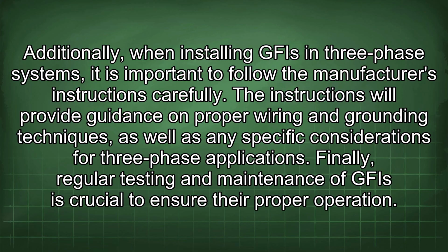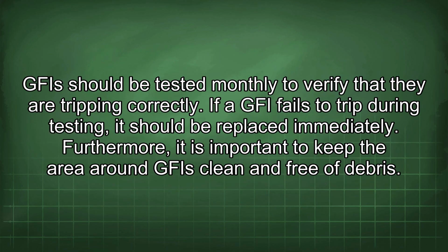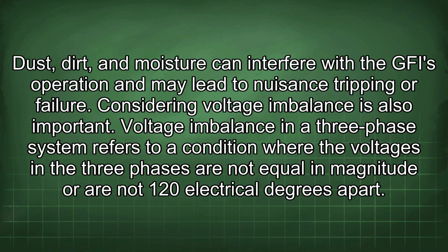Finally, regular testing and maintenance of GFI is crucial to ensure their proper operation. GFI should be tested monthly to verify that they are tripping correctly. If a GFI fails to trip during testing, it should be replaced immediately. Furthermore, it is important to keep the area around GFI clean and free of debris. Dust, dirt, and moisture can interfere with the GFI operation and may lead to nuisance tripping or failure.